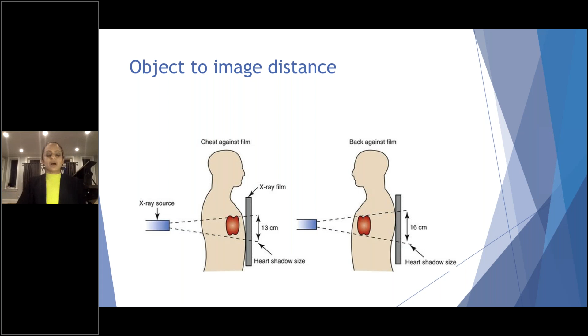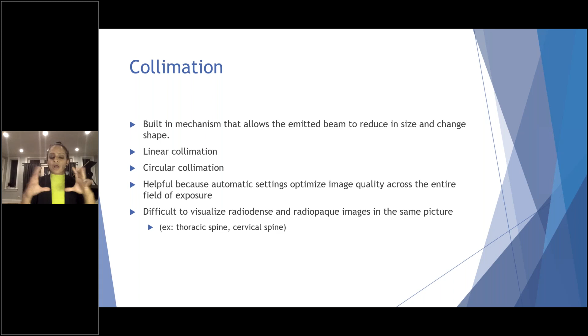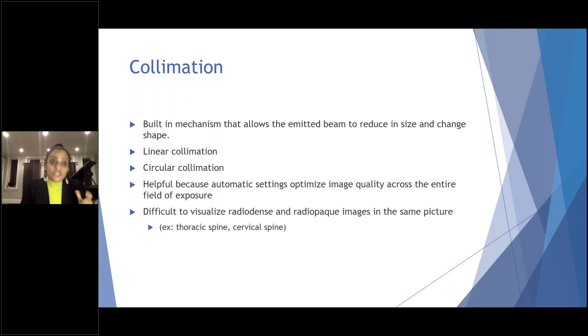We'll talk about collimation, which was the circle with purple buttons on our little control panel. It's a built-in mechanism that allows the emitted beam of X-rays to reduce in size and change shape. For the most part, it's linear or circular collimation. This is helpful because automatic settings optimize the image quality across an entire field of exposure. So if you have a small thing that you're X-raying and then you have all this air outside of it, it doesn't optimize the quality of your contrast dye spread as well, and that's when collimation can come into play. It's also difficult to visualize things that are radio dense and radio opaque in the same picture.